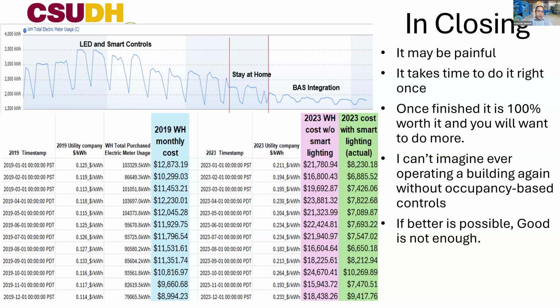And just like Adam had said, the cooling savings is where it's at, right? The lighting's great, but shutting down your chiller plant or not having to start up a second chiller because you just reduced your occupancy by half is huge. Next slide. And that's it. Thank you. Again, think about it. If better is possible, good is not enough. Let's all keep pushing the envelope.